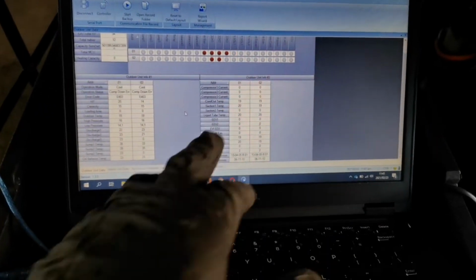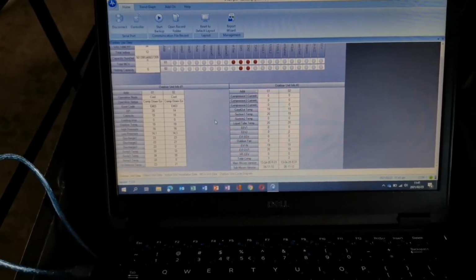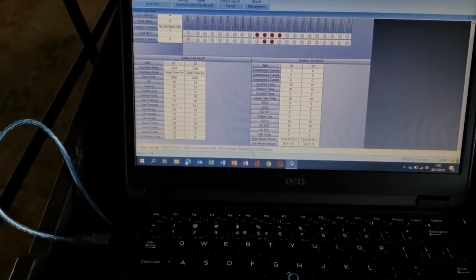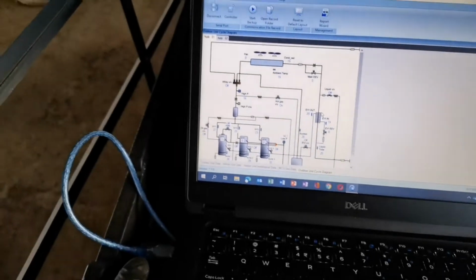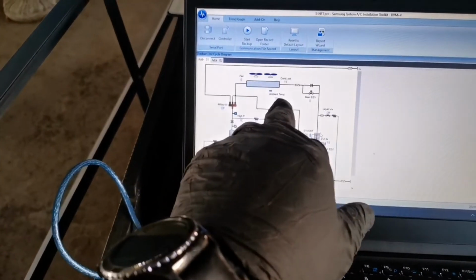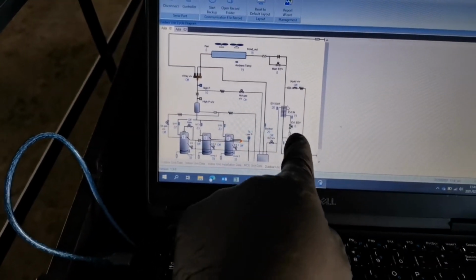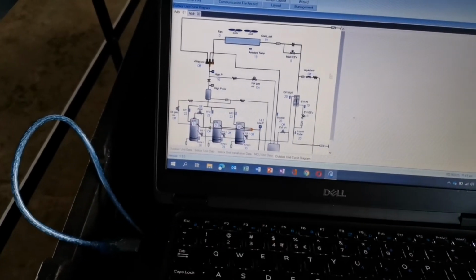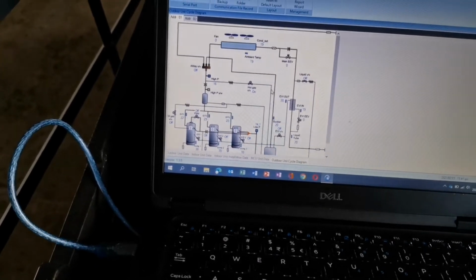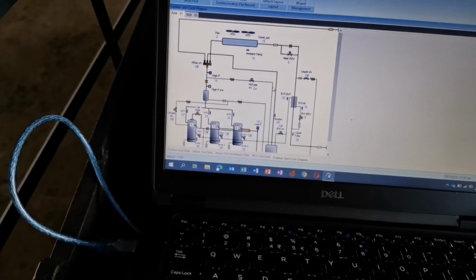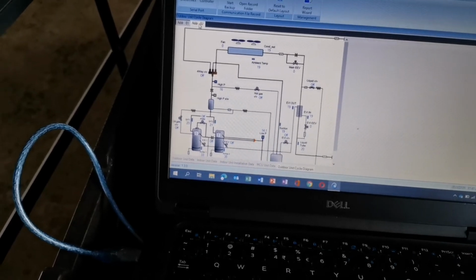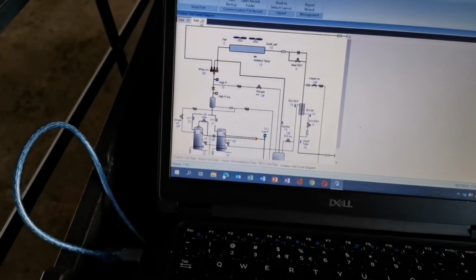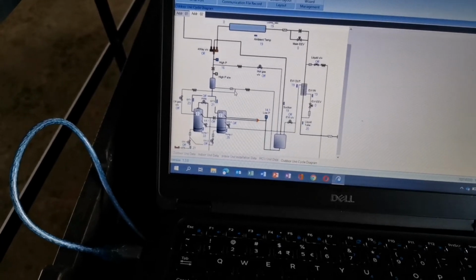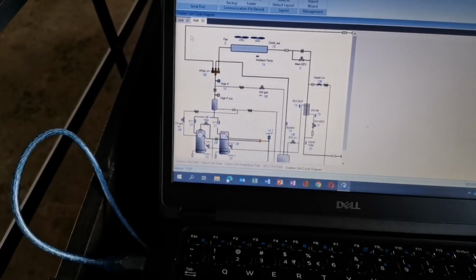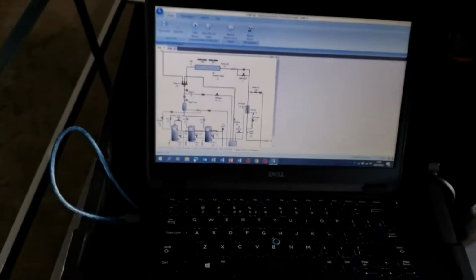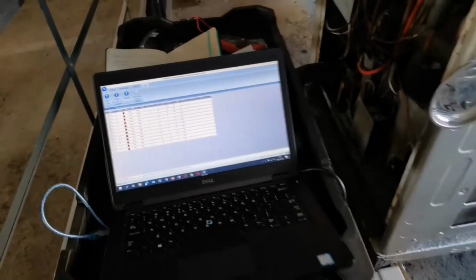So what we're going to do is have a look at our sensor data and see exactly what's going on. Let's go to our outdoor unit cycle. That will show us our sensors. So ambient 19, 19. Nothing is jumping out that is below freezing right now. So what I'm going to do is reset that. Let's just confirm that before I do that. Yeah, all the temperatures right now seem fine. So let me go ahead and reset that.